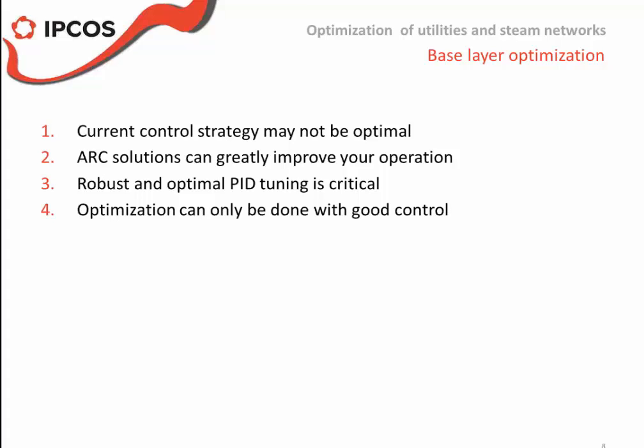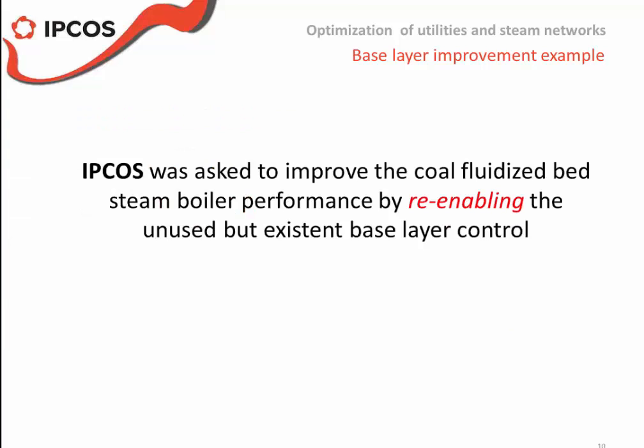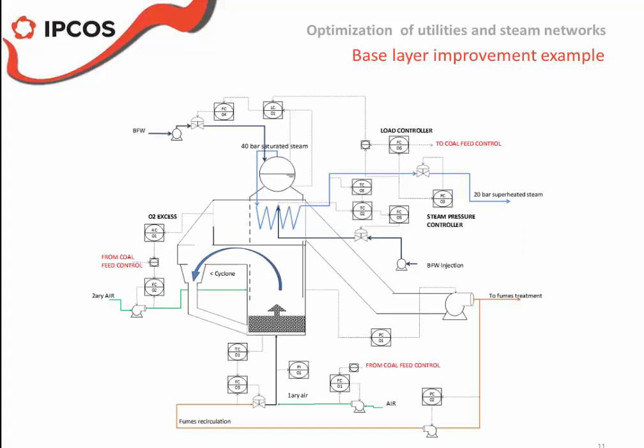We have a first case study at a utilities plant in France. Here we did a base layer improvement. We were asked to improve the coal fluidized bed boiler performance by re-enabling unused but existent base layer control. In other words, almost every single PID loop was in manual, and attempts to make them work had not been successful, but we were able to re-enable the whole base layer system.